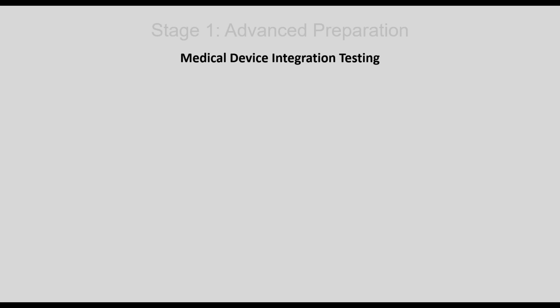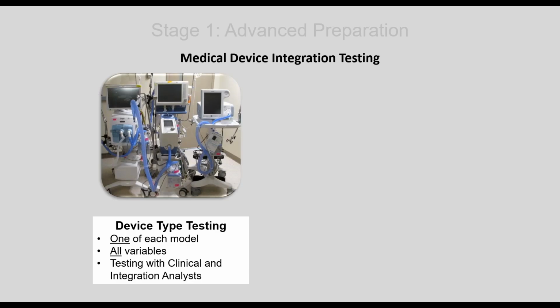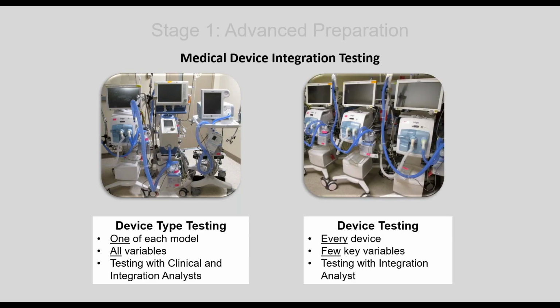So medical device integration testing. We're not getting too pushed for time, but I just want to keep going. What we do is device type testing for each model. Here we have three different ventilators, so we test each ventilator to make sure we map all the parameters. And then before deployment, we actually test each ventilator. We do that because when they're deployed, we know that we've tested each device, not just the model type, but each device. It's a little daunting, but you can do it. We do the same thing with patient monitors.